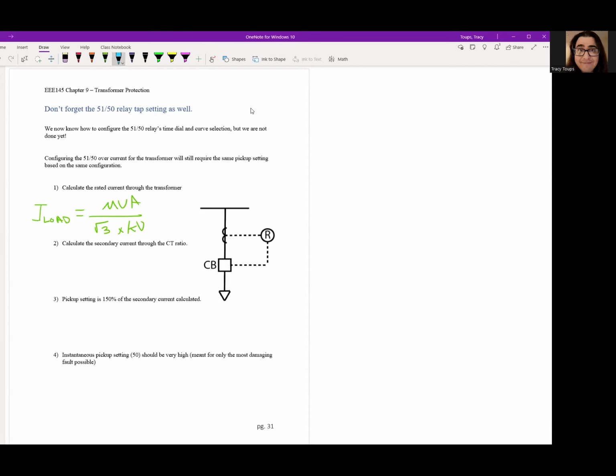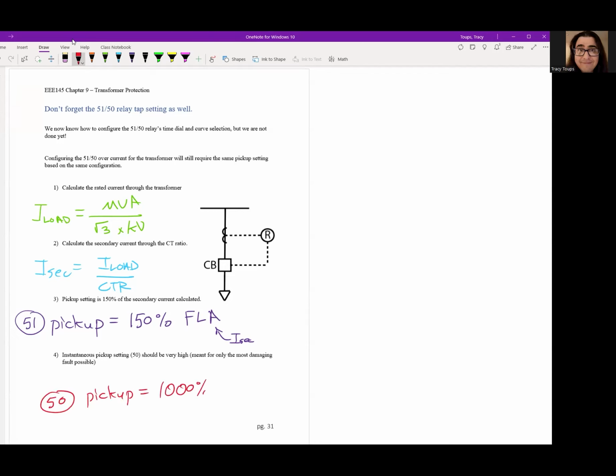Once you find the load current, calculate the secondary current through the CT ratio. Remember, the secondary current is always the load current divided by the CTR, which was hopefully chosen for you, or you choose the correct one. Then next, you find a pickup value for your 51 relay. The 51 element pickup value is always 150% full load amps. So whatever your I secondary is, that's your full load amps. And then lastly, your instantaneous pickup, your 50 pickup, which should be very, very high. This is typically about 1000% full load amps, which is again your I secondary. Okay, so it's a rehash of how to do overcurrent settings. That's pretty much all the major settings you have for transformer differential. I think you guys are pretty much set on that part.